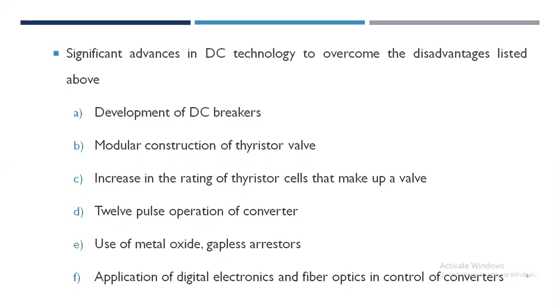It can be said without exaggeration that complexity of control does not pose a problem, and it can actually be used to provide reliable and fast control of power transmission, not only under normal conditions but also under abnormal conditions such as line and converter faults. This has removed the need for DC current interruption in two terminal links. Even for multi-terminal operation, the requirements of current rating of DC breakers are modest due to effective converter control.